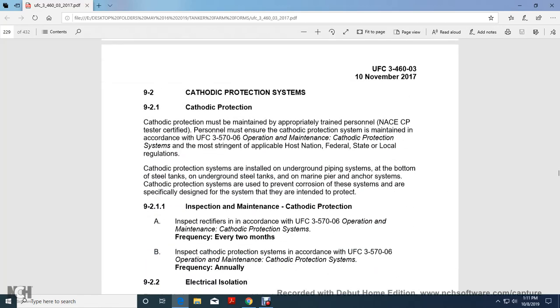Cathodic protection systems, 9.2.1. Cathodic protection must be maintained by appropriate personnel, who must ensure the cathodic protection system is maintained according to UFC 3-570-06, Operation and Maintenance: Cathodic Protection Systems, and the most stringent applicable host nation, federal, state, and local regulations. Cathodic protection systems are installed with underground piping systems, the bottoms of steel tanks, underground steel tanks, and marine pier anchor systems.